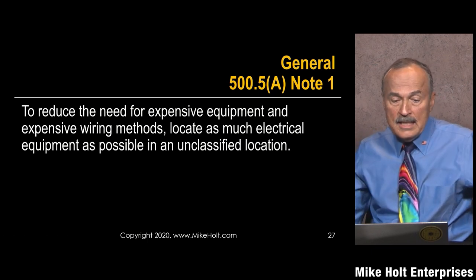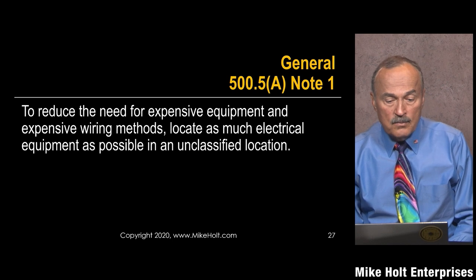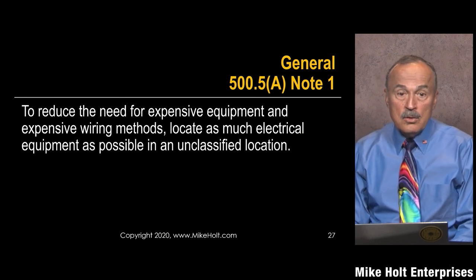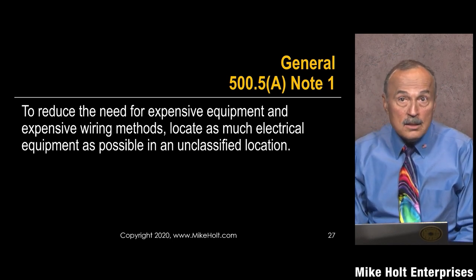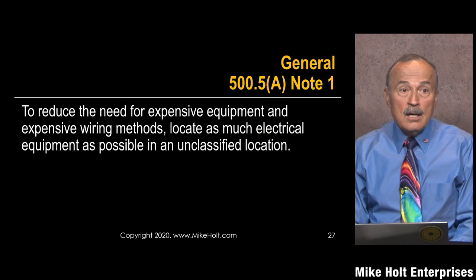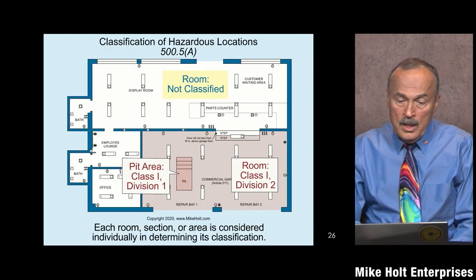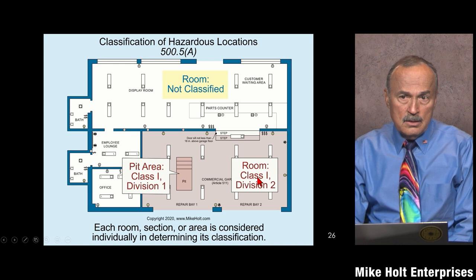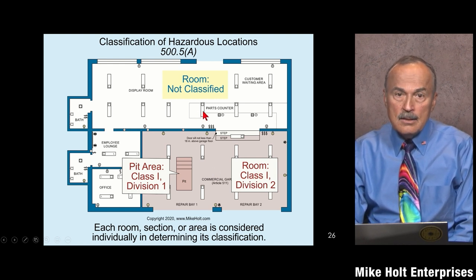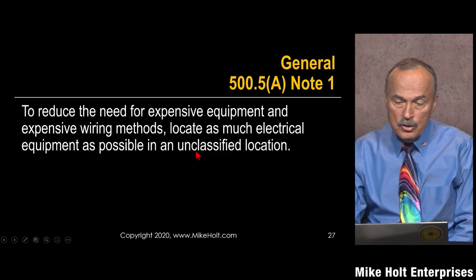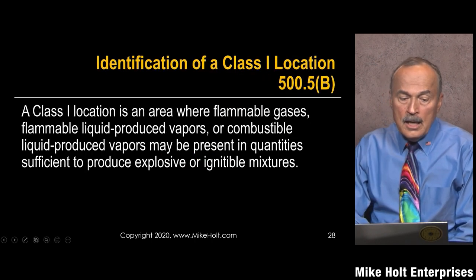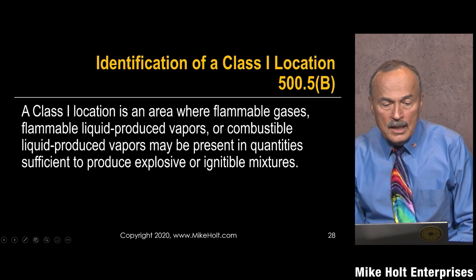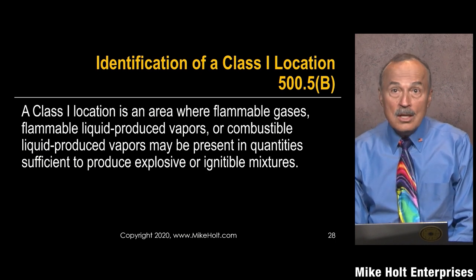Informational note: to reduce the need for expensive equipment and expensive wiring, locate as much electrical equipment as possible in an unclassified location. If you can put the disconnect outside, don't put it inside that classified room. That is a good decision.